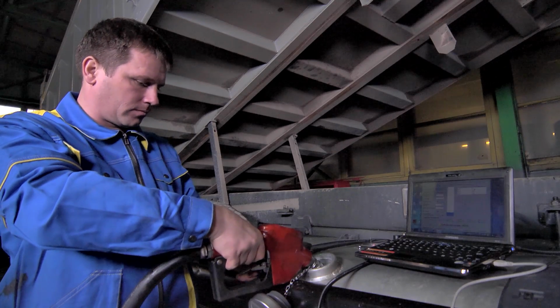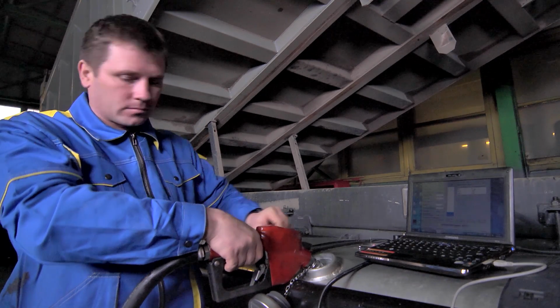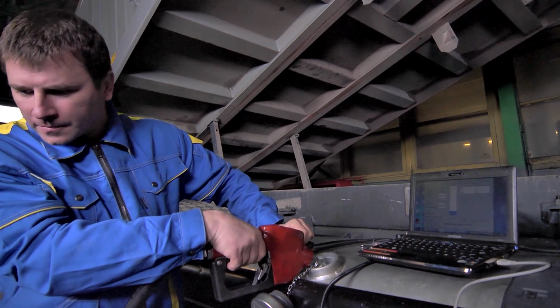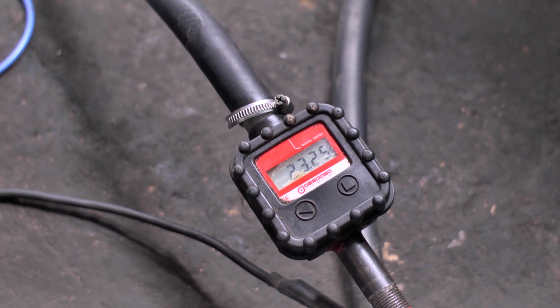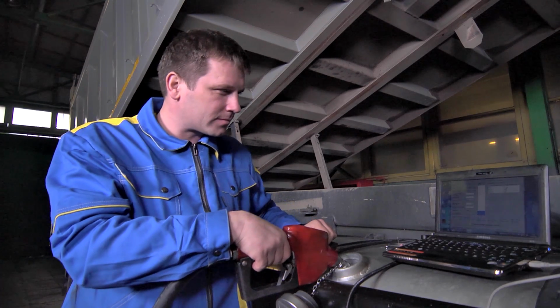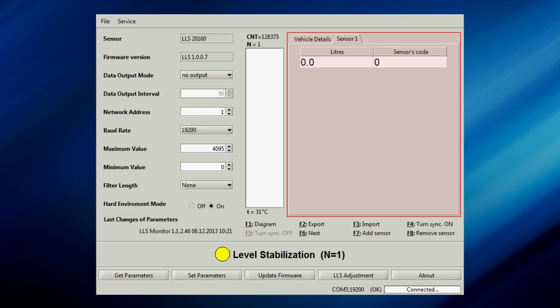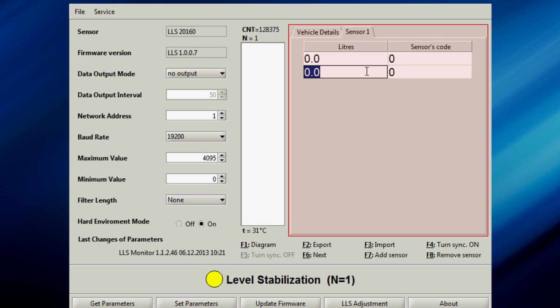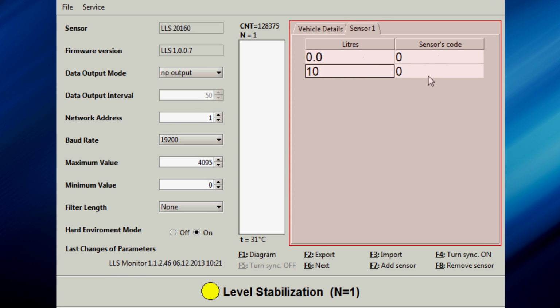During the tank calibration process, fill the tank with fuel in portions and record the tank volume values and the corresponding sensor level readings in the calibration table. It is very important to record the readings only after the fuel level has stabilized in the LLS monitor application. After recording new values, press the Enter key.